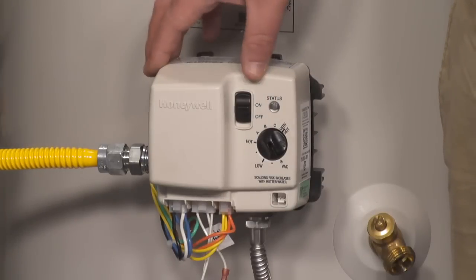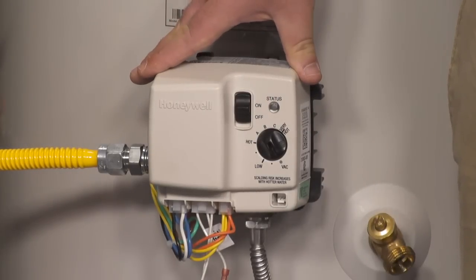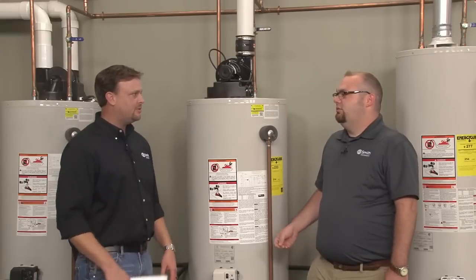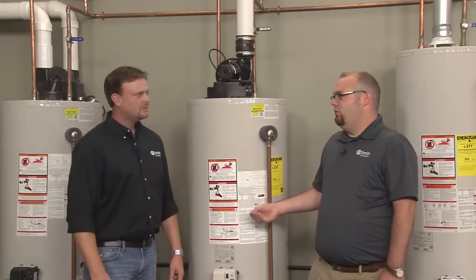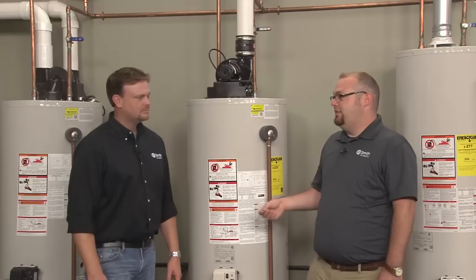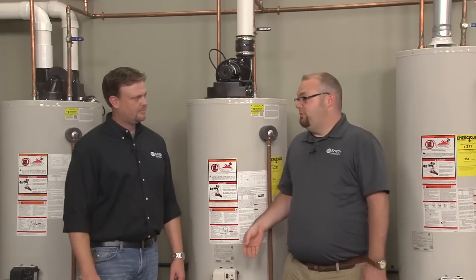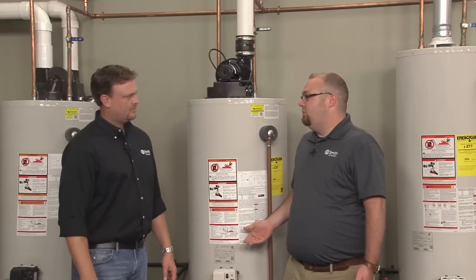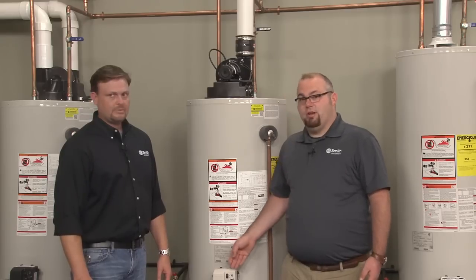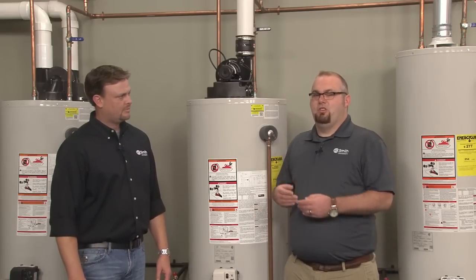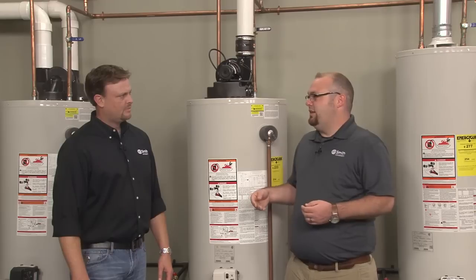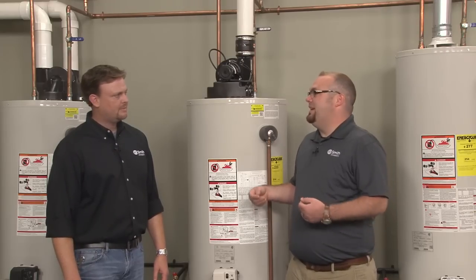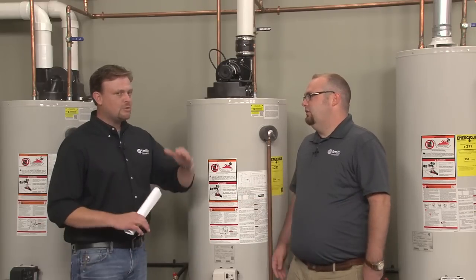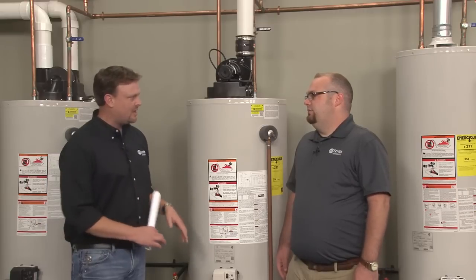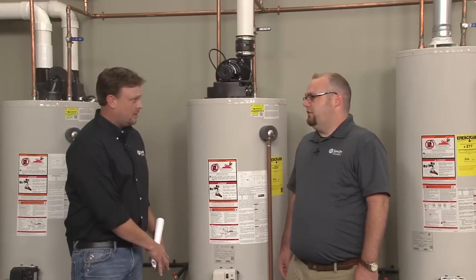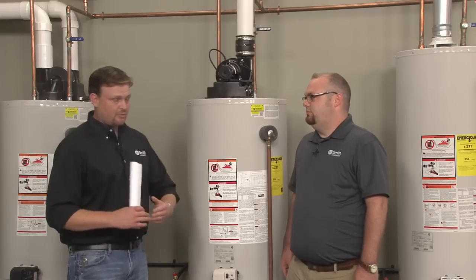Now, if it locks out, do I have to replace this? That's another question we usually get. Yes, I'd recommend replacing it. Temporarily, you may be able to reset the heater and get it back up and running. But once that sensor trips, I do recommend replacing it, because it's going to become more sensitive, which means it's going to be safer, but it's going to be easier for it to lock out. So once the resistance comes down, we have to check that with a multimeter, and make sure that it's in the correct range.